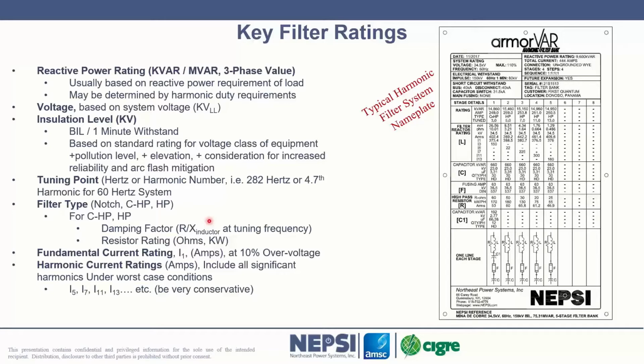And I make that statement, it's an output rating. What is the output rating of the harmonic filter? It's not the amount of kvar installed. Remember that the kvar outputs from the capacitors inside a filter bank, generally speaking, will be greater than the overall output of the harmonic filter system. So we're using higher voltage, higher kvar rated capacitors inside a harmonic filter.